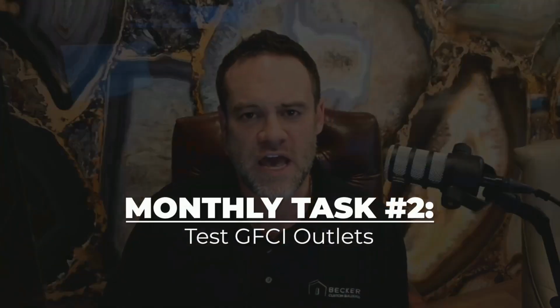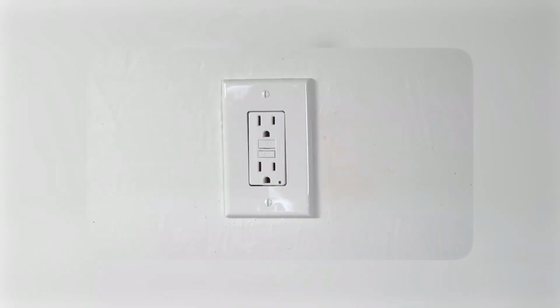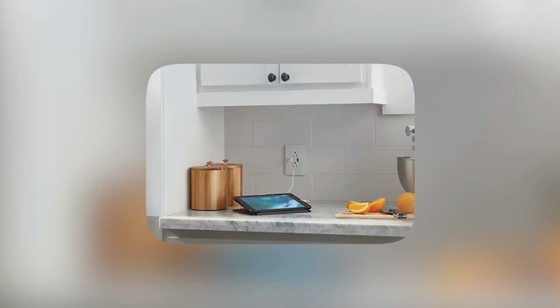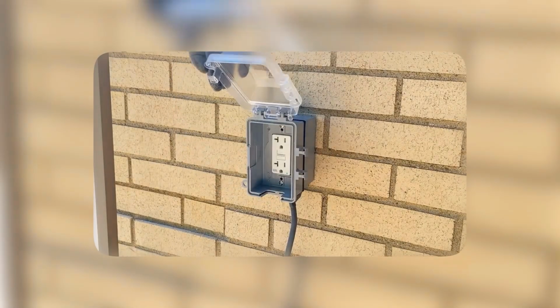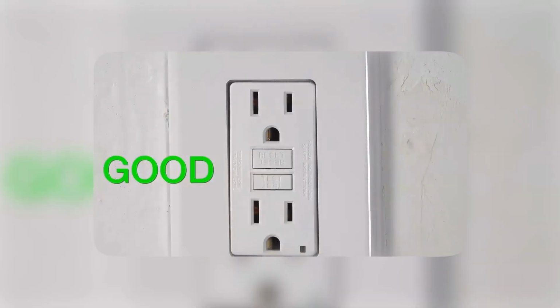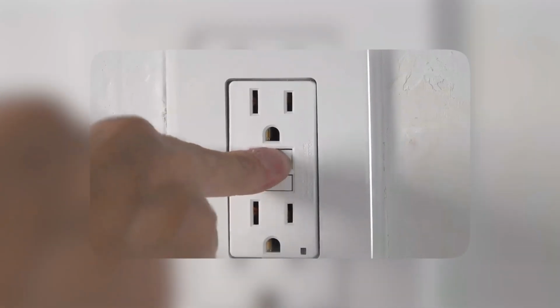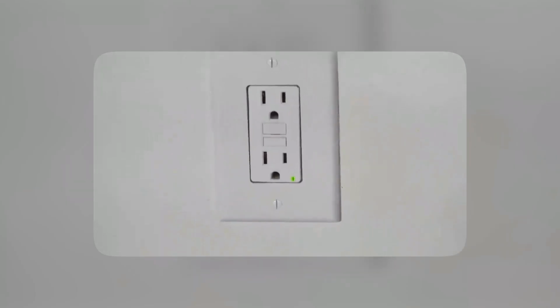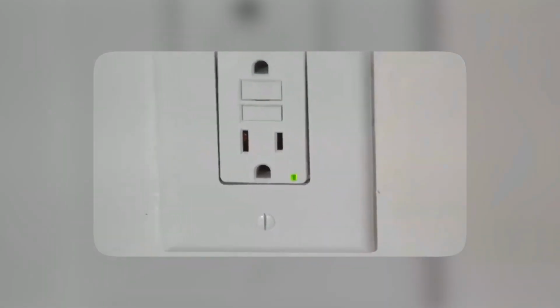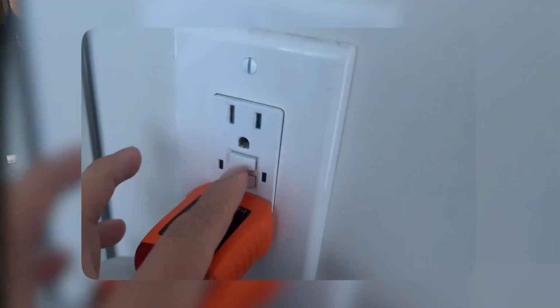Test GFCI outlets. These outlets are usually in places like bathrooms, kitchens, garages, or even outside areas. Press the test button to ensure the outlet shuts off, then press reset to restore power—sometimes they even have a light for reference. Alternatively, you can use a GFCI tester, like one from Klein Tools, that will trip the outlet and ensure it resets properly.